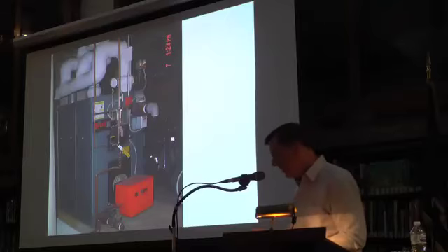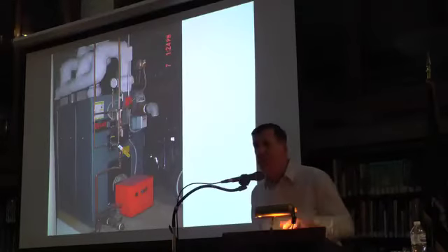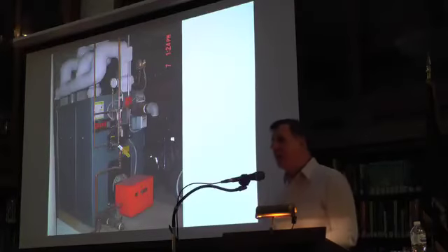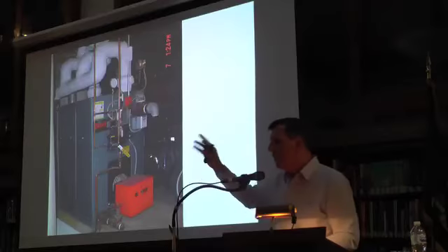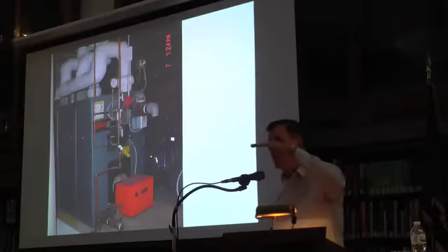So the system needs to be clean. And the skimming gets rid of the oil, particularly on startup. So once the boiler goes in, you give it a week or so to run, and then you go back there, and you just shut the boiler off, and you turn on the cold water, and you let it drift to the center of that T.